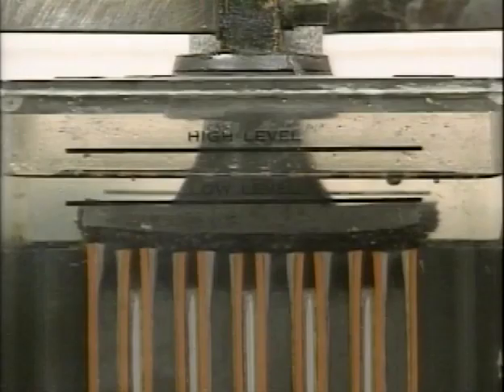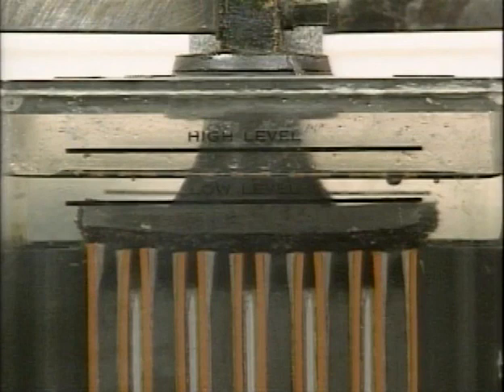The term specific gravity for a substation battery cell refers to the density of the electrolyte in the cell in relation to the density of water. A cell's specific gravity is normally an indication of its state of charge.